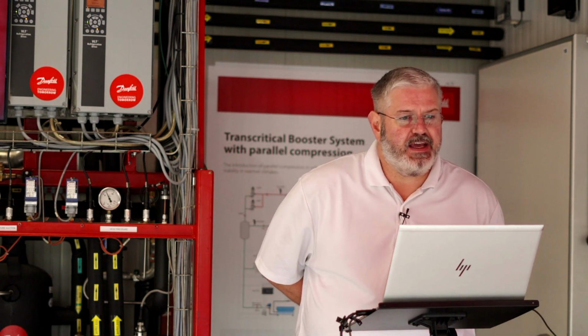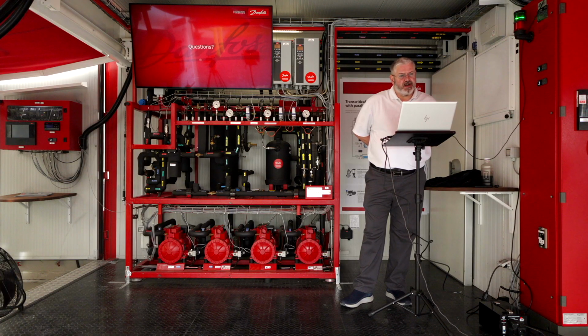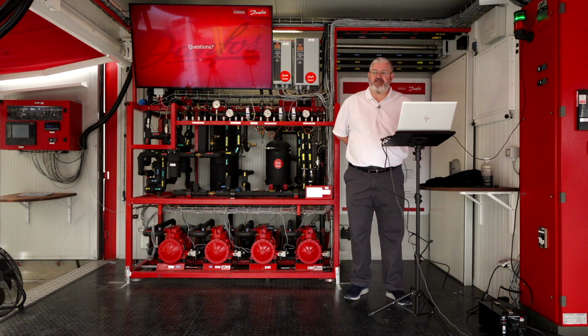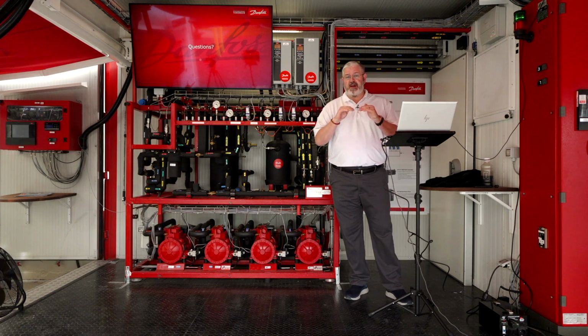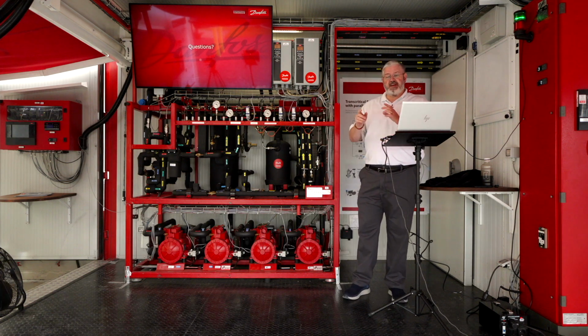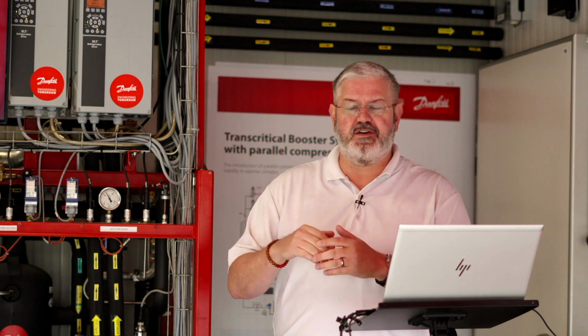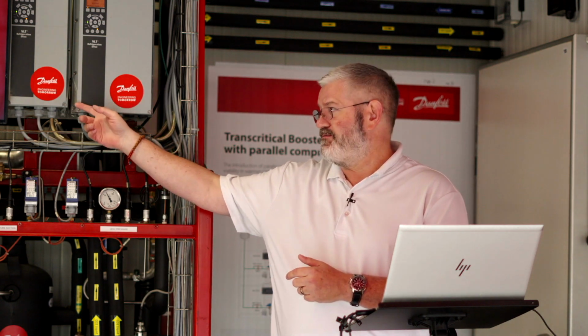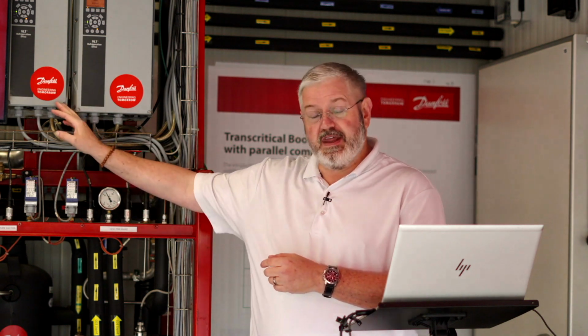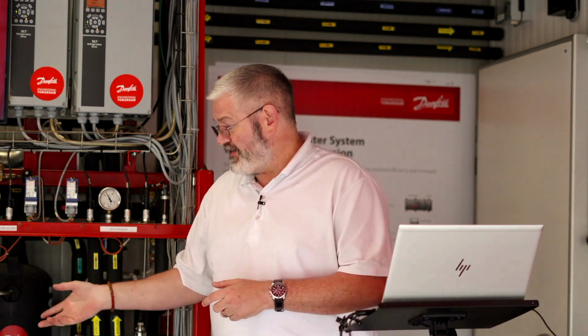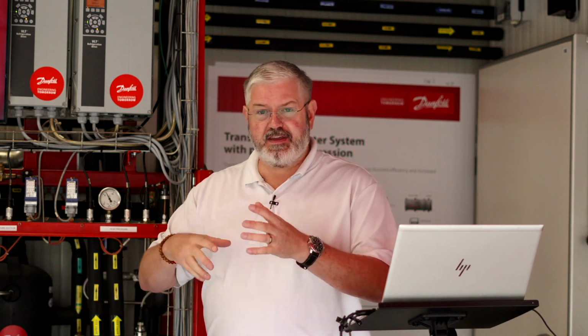So we have a question. Have you seen any issue with the compressors vibrating so strongly at a certain hertz on the VFD? Yes, I have. So the question is, have we seen vibration issues at random hertz from the VFD? And the answer is yes. I mentioned earlier having seen one with the discharge line broken. The solution to that, other than it not being properly supported on the system, was that they also wound up skipping like 41 to 44 hertz or something. That's where the vibration was occurring. And in the VFDs, you're able to program in steps to skip. So you can program it so that it'll skip certain hertz that are causing vibration. But yes, that does still happen on CO₂. I think that's with any inverter and compressor scenario. Every now and then you get that magic setup that causes some issues, and you use hertz step skips to address it.